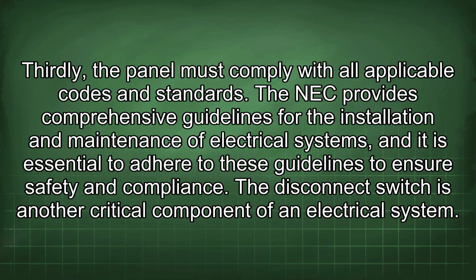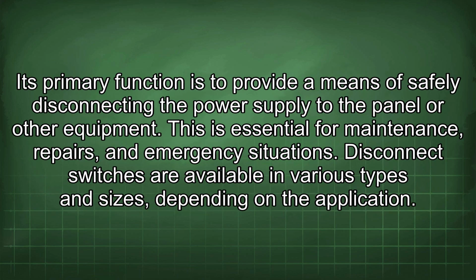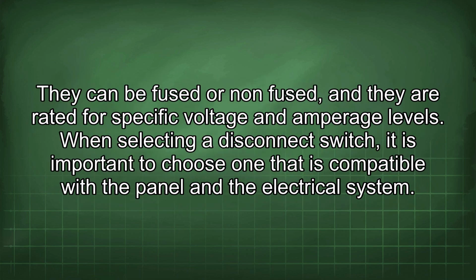The disconnect switch is another critical component of an electrical system. Its primary function is to provide a means of safely disconnecting the power supply to the panel or other equipment. This is essential for maintenance, repairs, and emergency situations. Disconnect switches are available in various types and sizes depending on the application. They can be fused or non-fused, and they are rated for specific voltage and amperage levels.